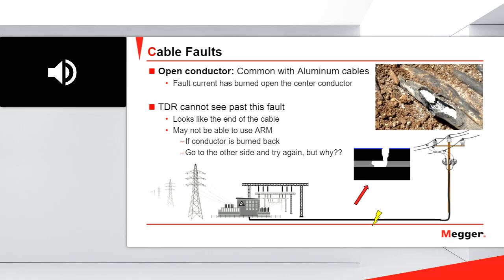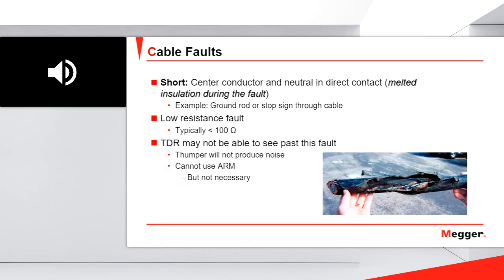And the last fault that I would like to mention is the short. Sometimes when we have a lot of current in the fault, the current will melt the insulation, and then there will be a contact between the conductor and the concentric. This is the other typical fault in medium voltage cables.